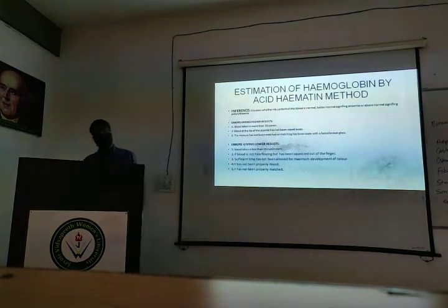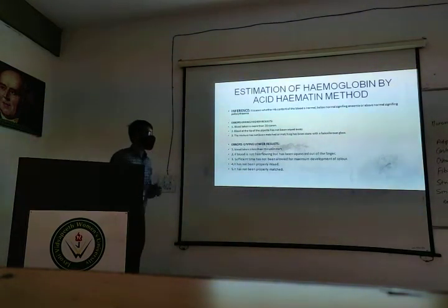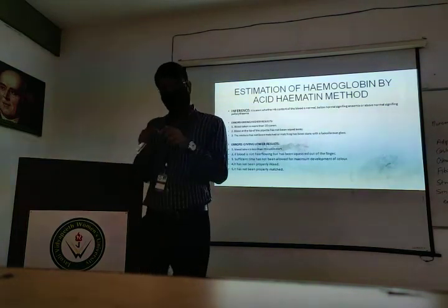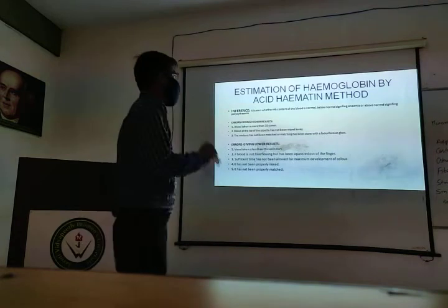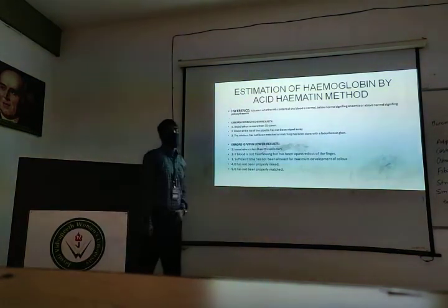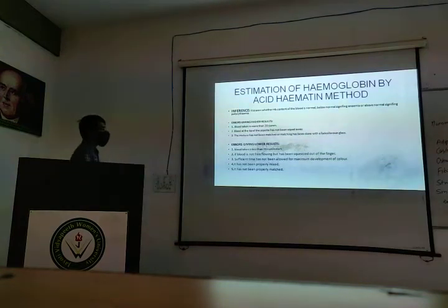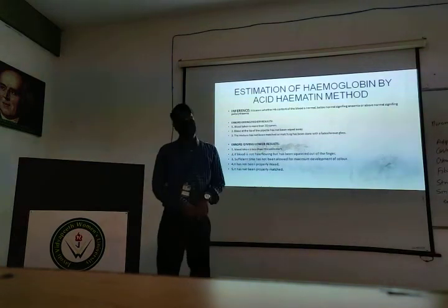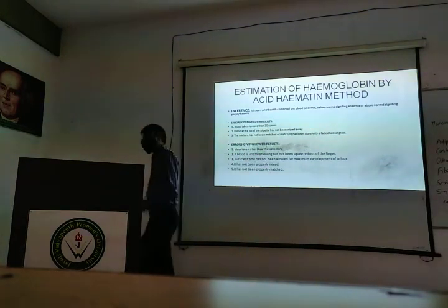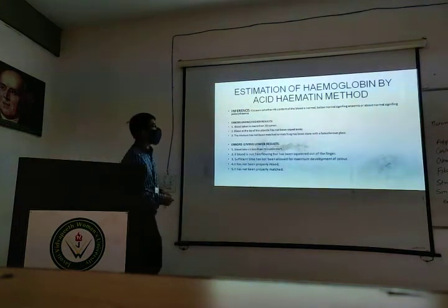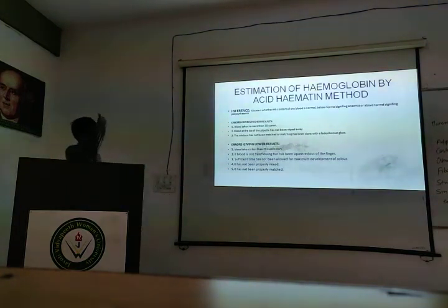If we don't wipe the blood at the mouth of the pipette, there will be some extra blood dropping in when we mix the blood with N/10 HCl. Third, the mixture has not been matched, or matching has been done with a faded brown color. If the comparator is defective, we can also get an error giving higher results.